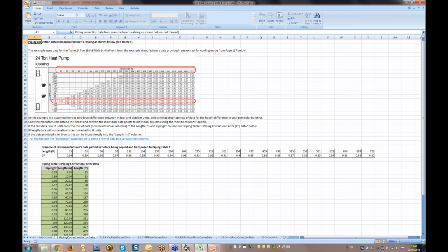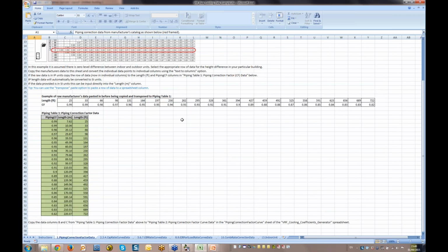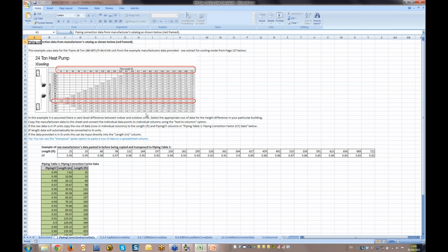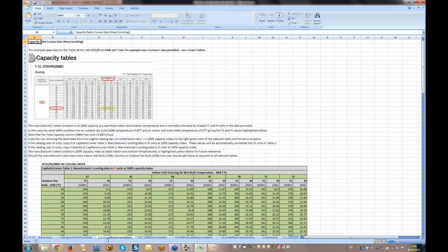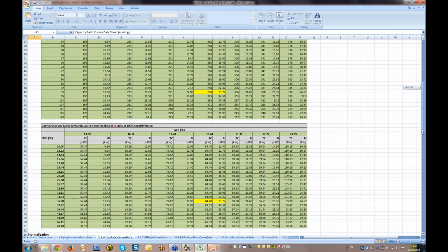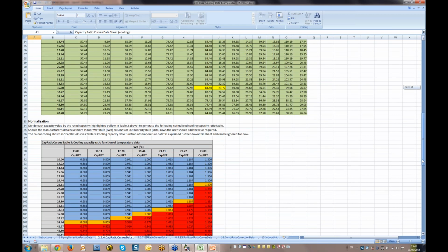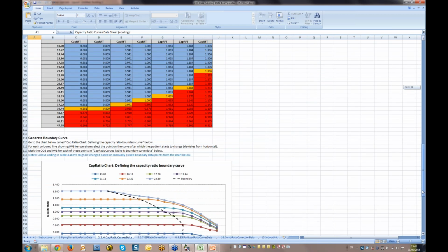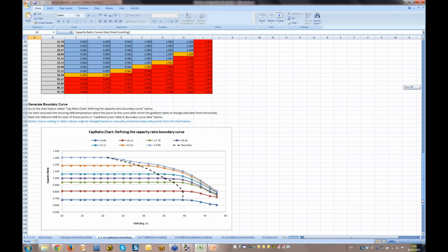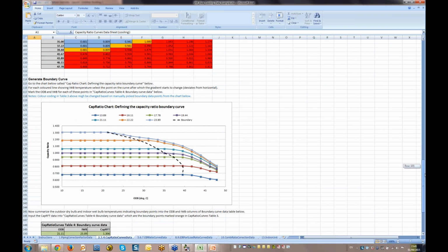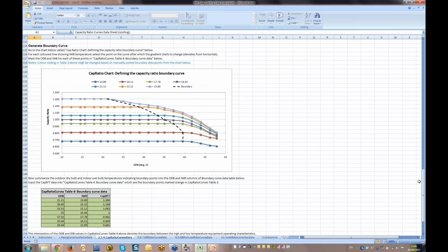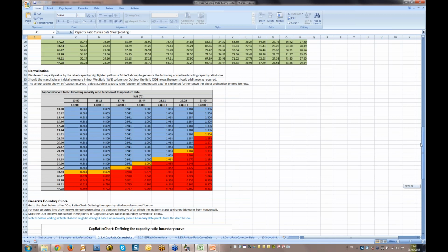The first tab relates to piping correction factors, and you can see that detailed instructions are provided to help you make sense of the inputs. In the second tab, you input data for the capacity ratio curves, as shown here. Below the data input table, you can see the capacity ratio boundary curve generated that governs how the VRF equipment operates under higher and lower temperature conditions. Again, Jim will expand on the use of curves later. That's probably sufficient just to give you a flavour of the spreadsheets for now.